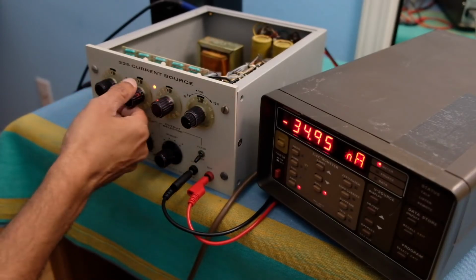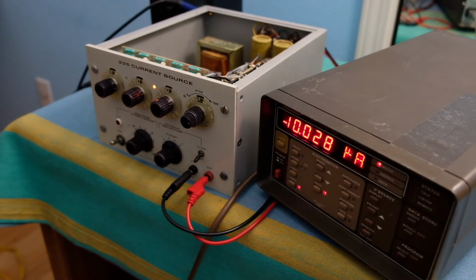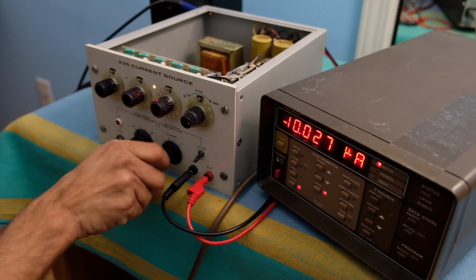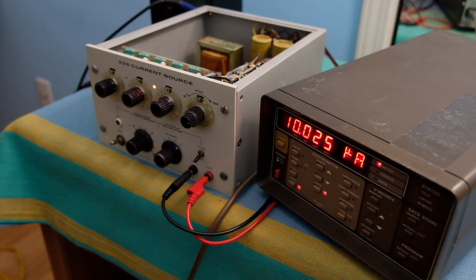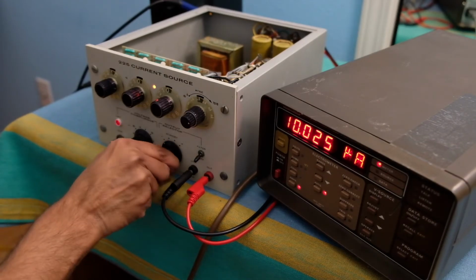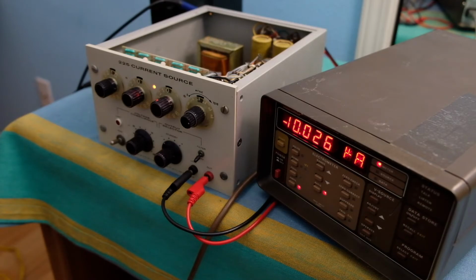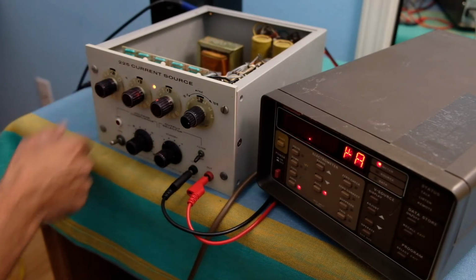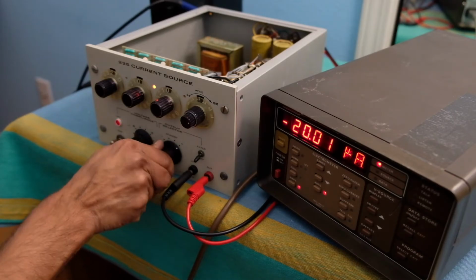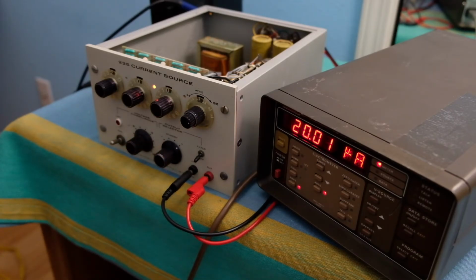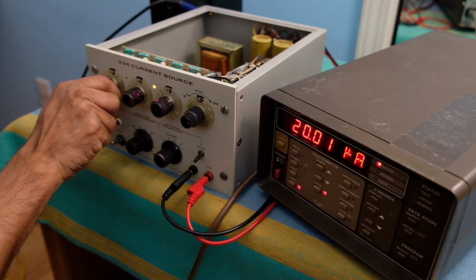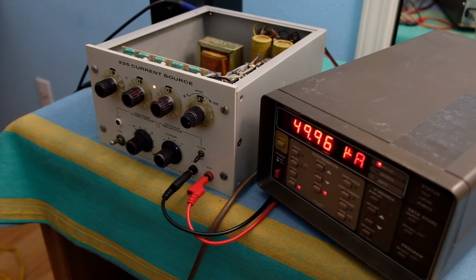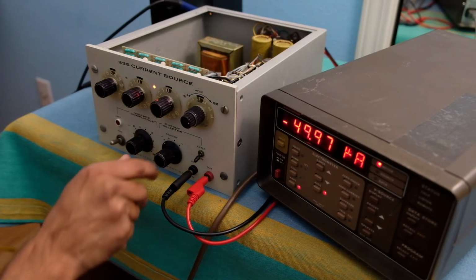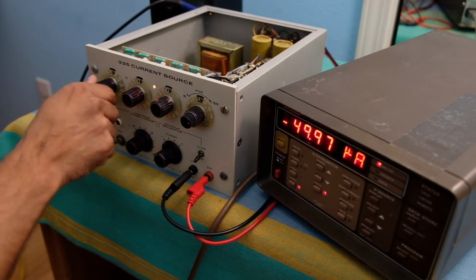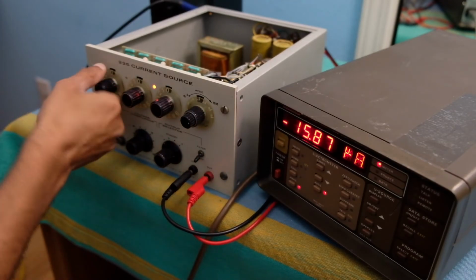Let's go to the 10 microamps. -10.03, +10.025, which is nicely balanced here. Perfect. 20, 20.01. Again, this is perfectly balanced on this scale. So, 50 microamps. These are the kind of ranges I would be operating in to test a lot of equipment. Looks good.